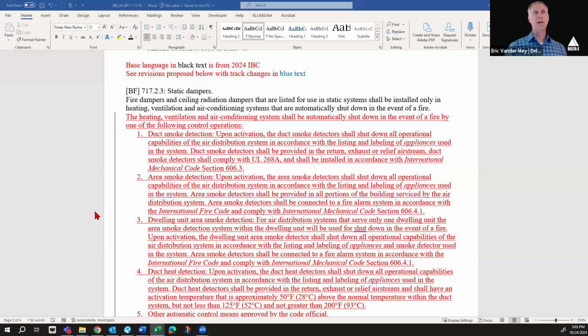And so that might not be the best means of shutdown. That's why item 4 is pretty specific that it has to be a listed system, and it has to be connected to a fire alarm system to do that - mirroring other language in the fire code and mechanical code sections for those shutdowns. Thank you.